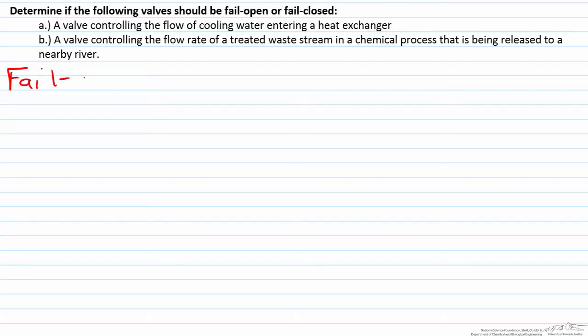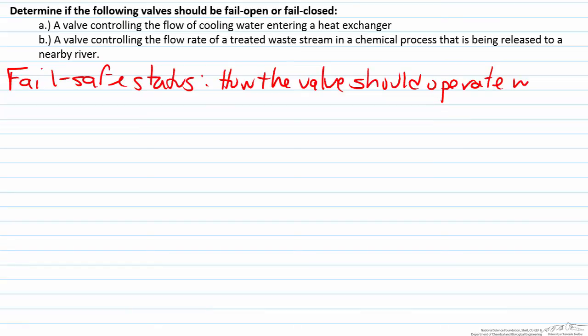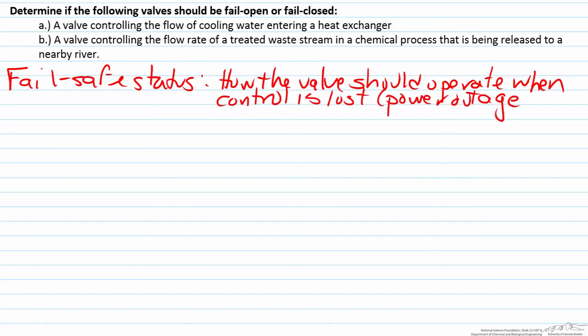The fail safe status represents how the valve should operate when control is lost. Typically control will be lost when there is a power outage or something similar. A good way to think about it is: if you lose power, how do you want your valve to operate? This is dictated solely by your process.